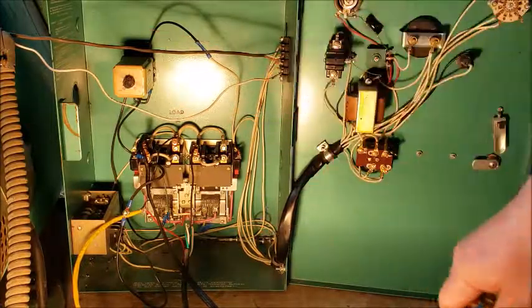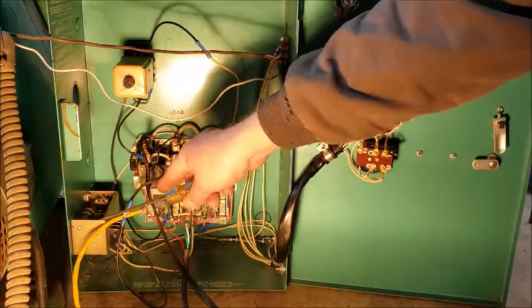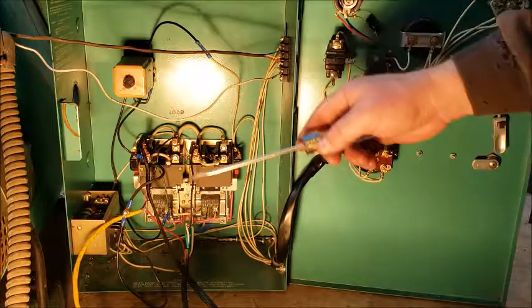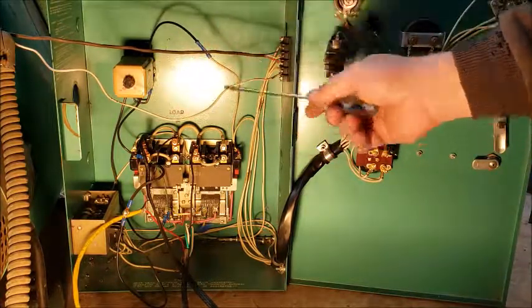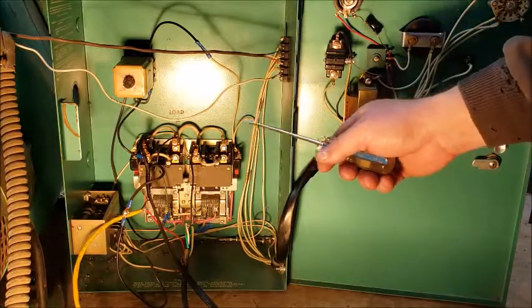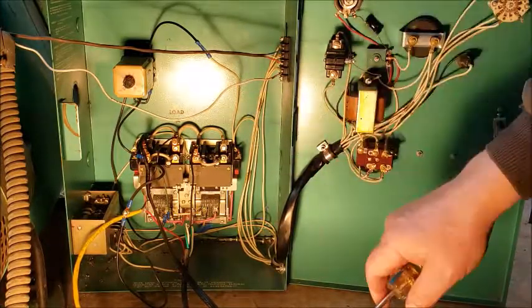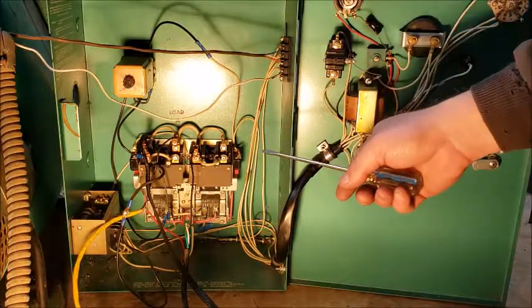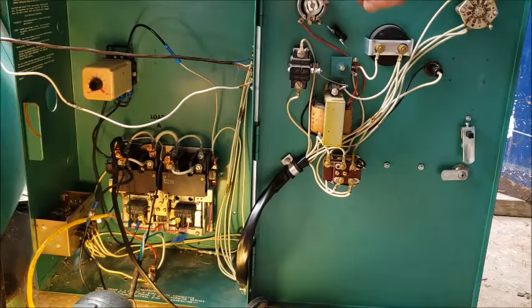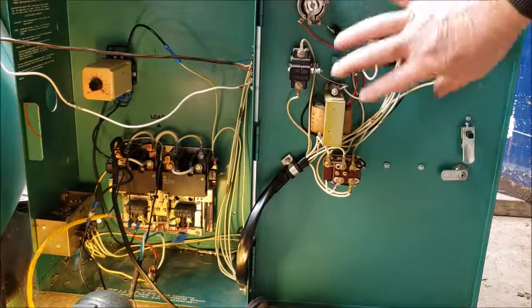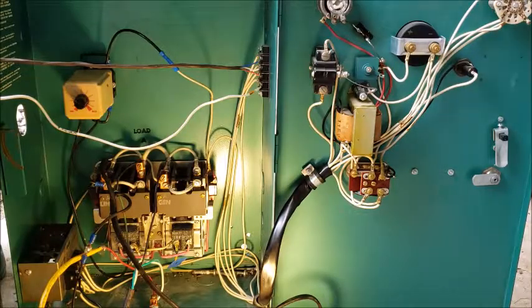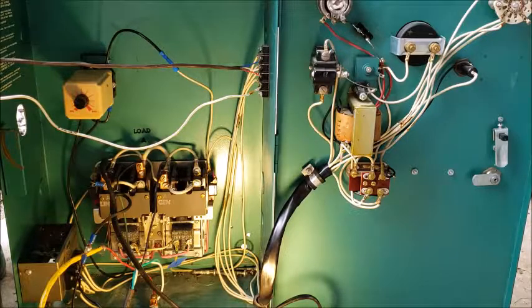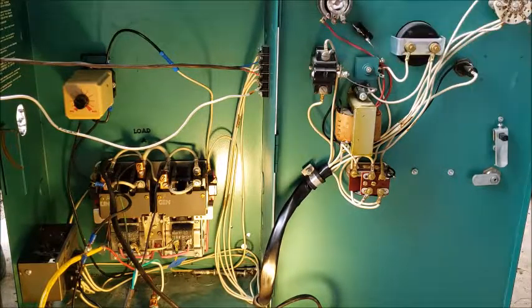This is a delay timer. And the way I got this box is it's hooked up to line voltage. I think I mentioned this before. So when line voltage is restored that counts down, it's like a 10 second timer. This, this, this and this are all part of the battery charging circuit for when the generator is just sitting. And so this charges the battery with a trickle charge.